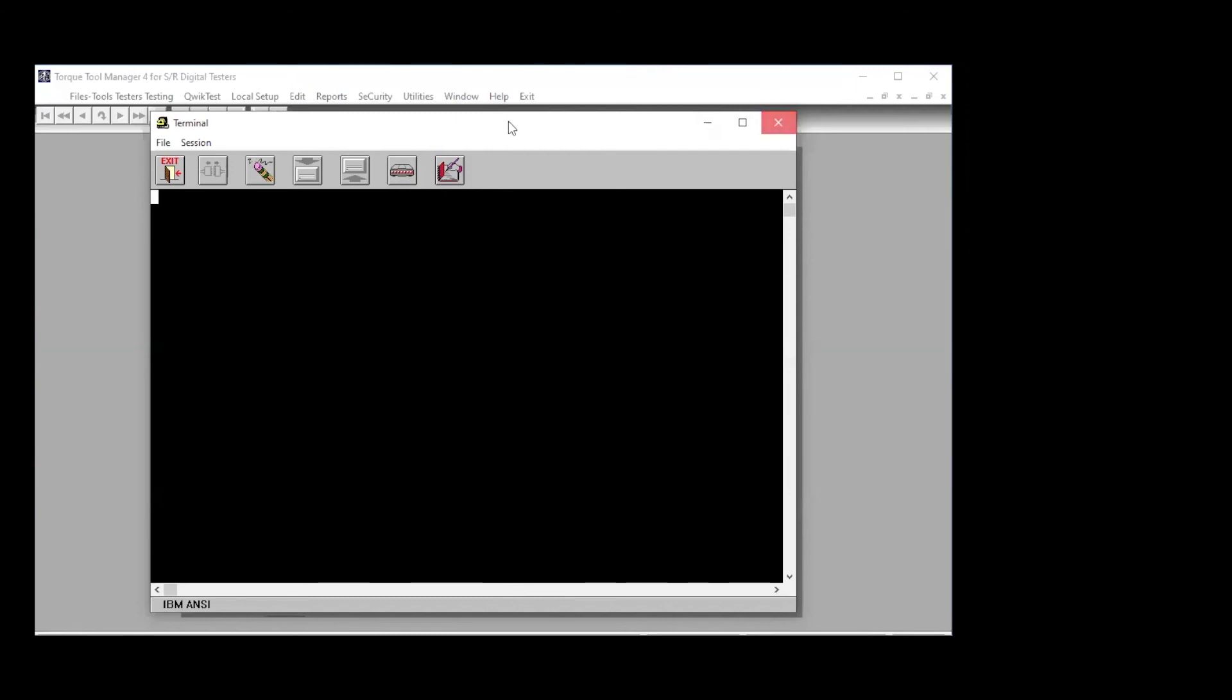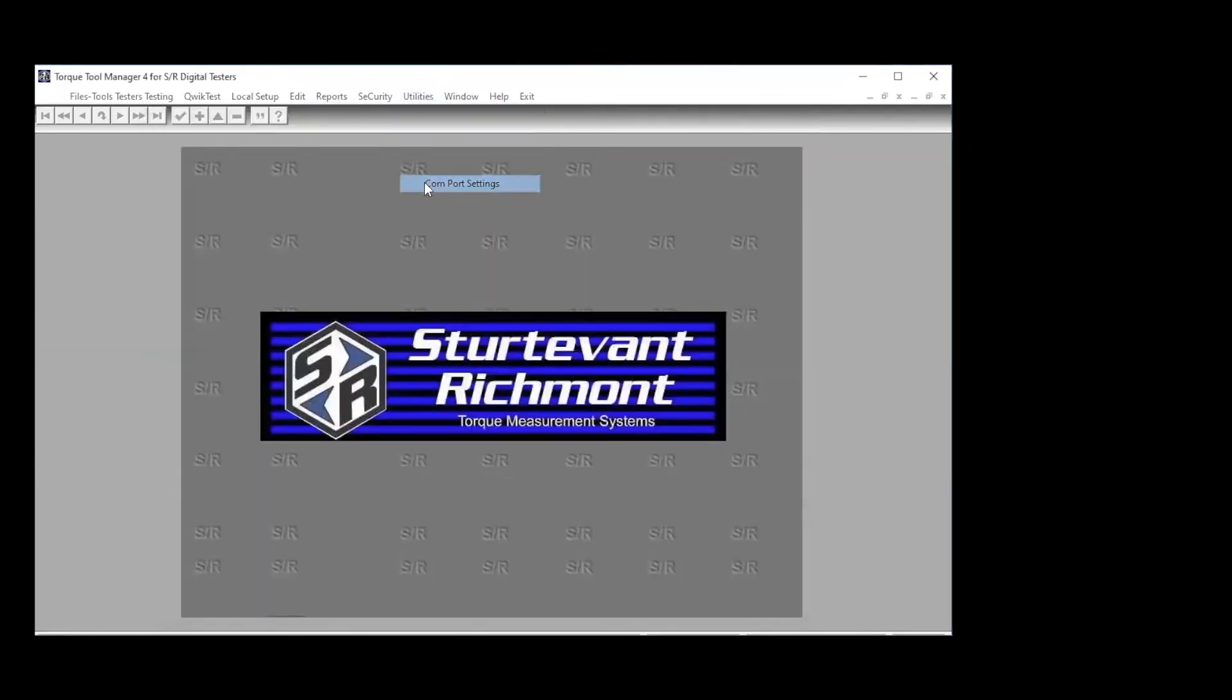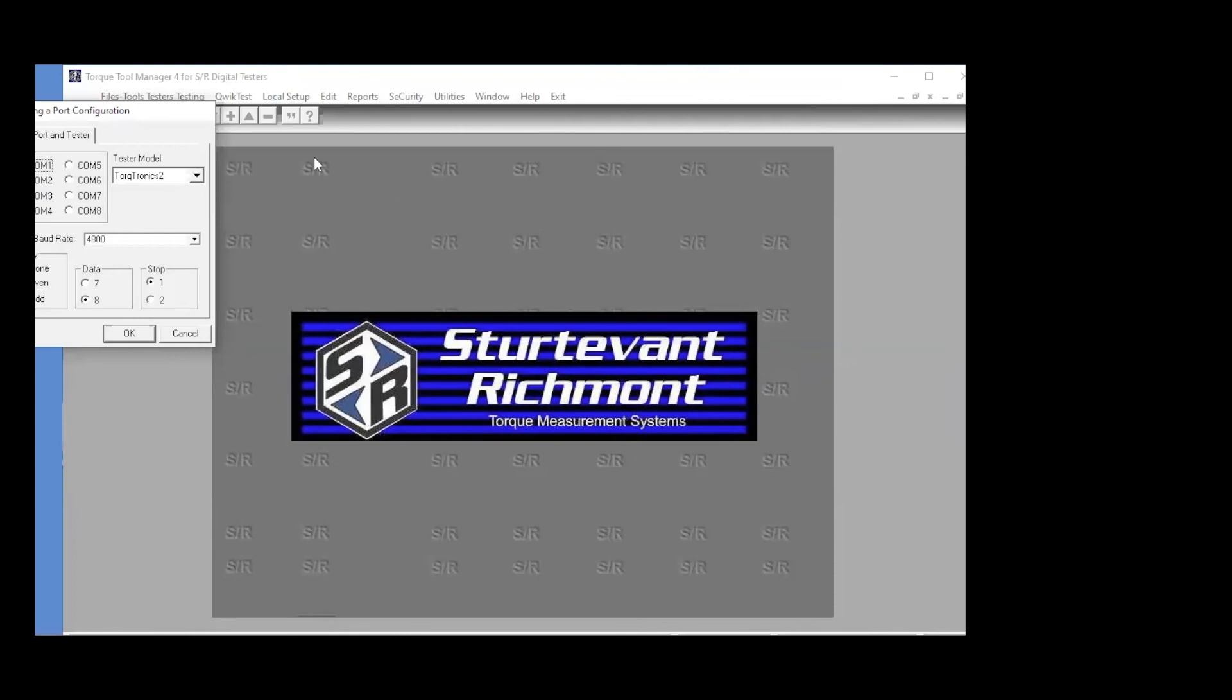And then the last thing that we want to show you here in utilities is the COM port settings. We know that this computer, all computers are different. The serial port is on COM port 3, so we use that. We're connected to the TorqTronics 2, and you can see if we're trying to find some other units we can identify them. We've got the baud rate, parity, the data, and the stop bits. So all of that's good.